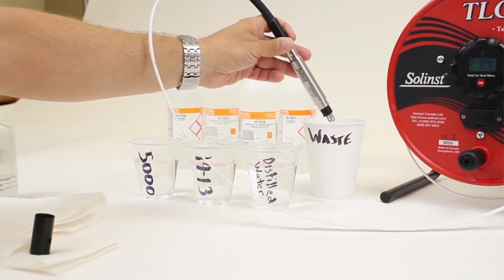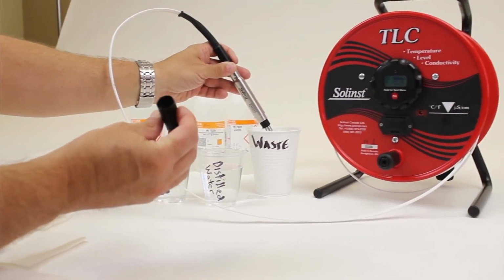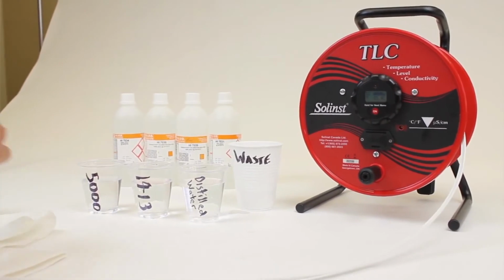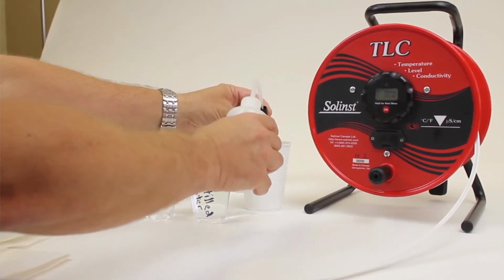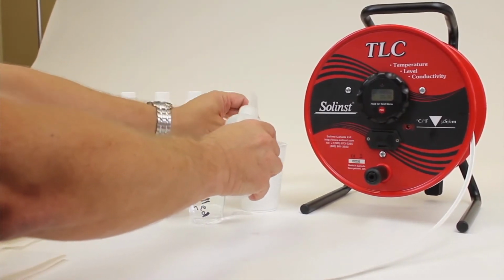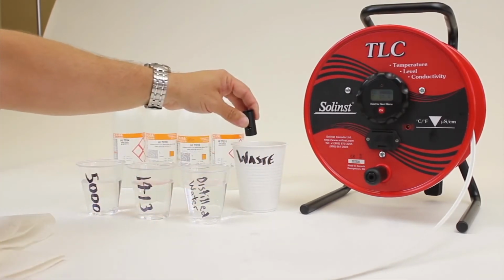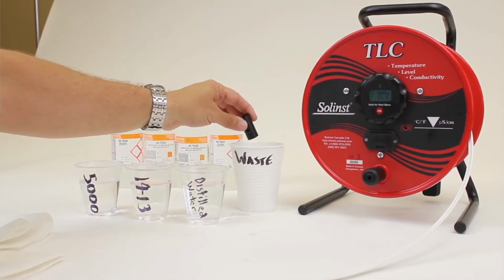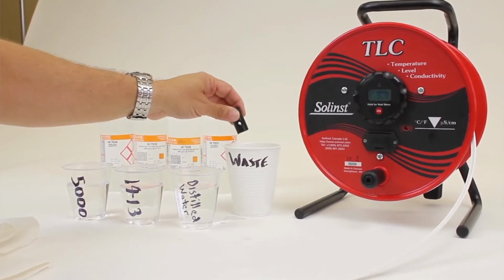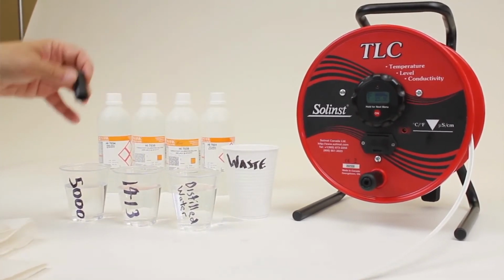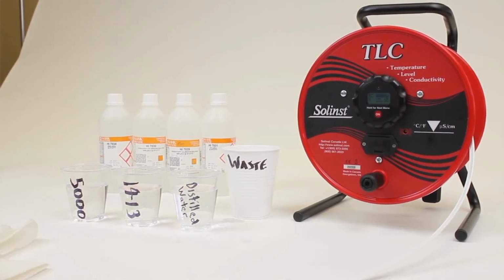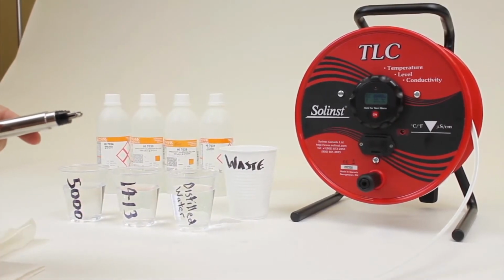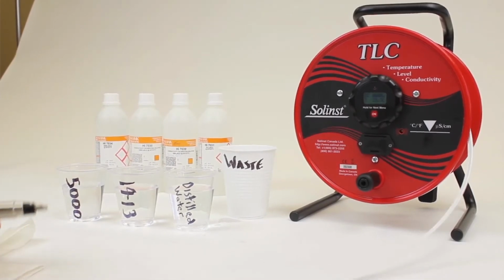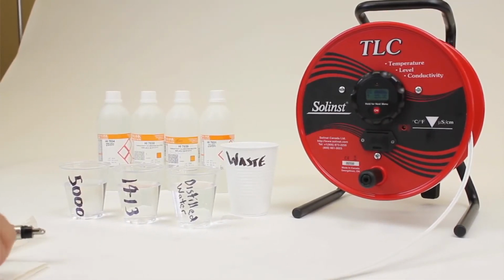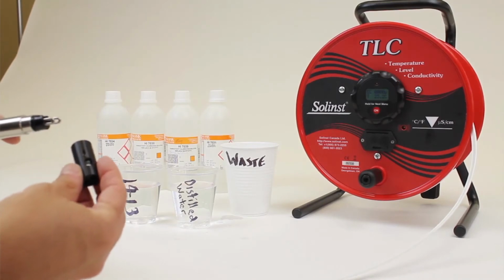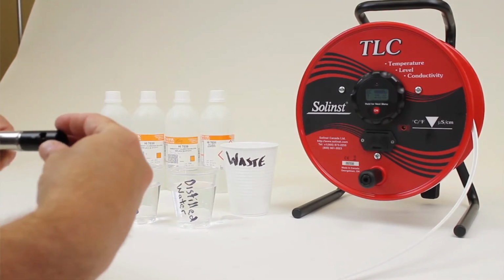Now normally what I would do at this point, again, clean the probe shroud, and that can be cleaned with a spray bottle or just pouring distilled water or any solution into it. Again, always finalizing with your distilled water, or in this case what I might do is pour some of the next calibration solution over the probe and the sensor itself, the shroud and the sensor itself. In this case I've got my 5000 microsiemens solution ready. I'm going to put the probe shroud back on the sensor tip.